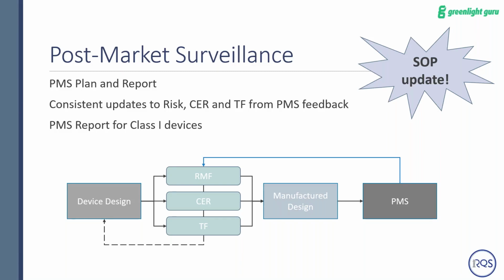This is also new for Class 1 devices. So previously, Class 1 devices didn't have as much requirements around post-market surveillance. So this is an update for those as well.